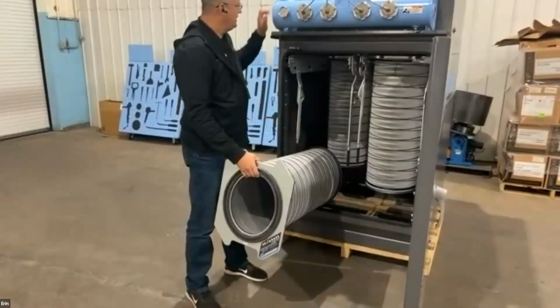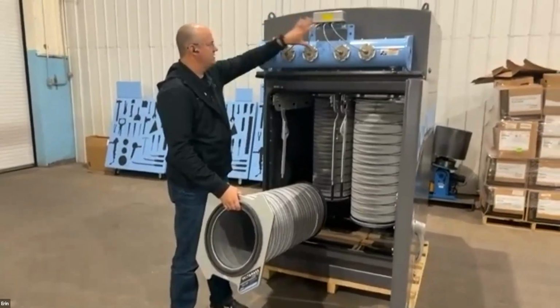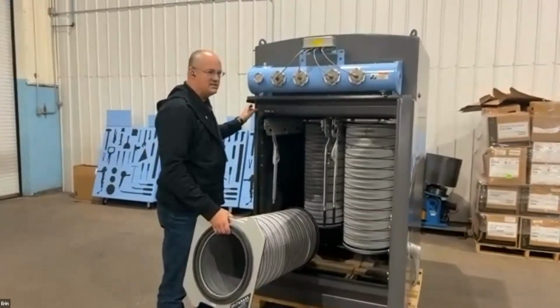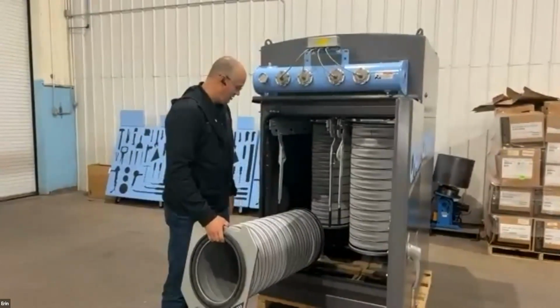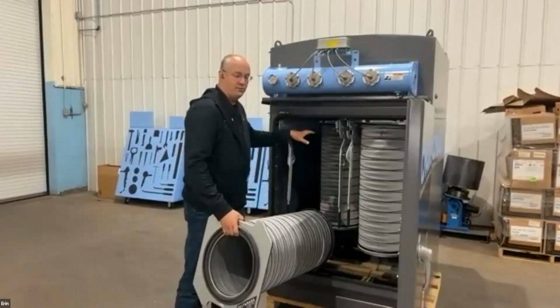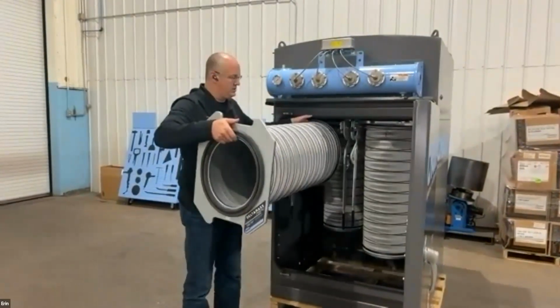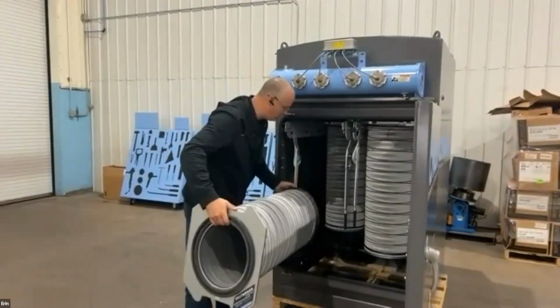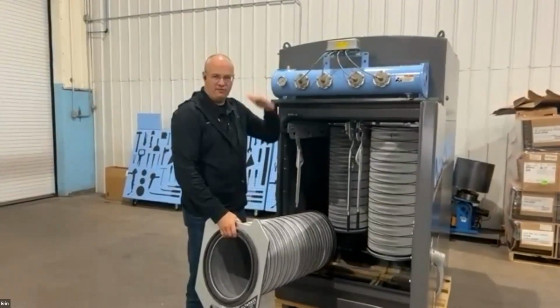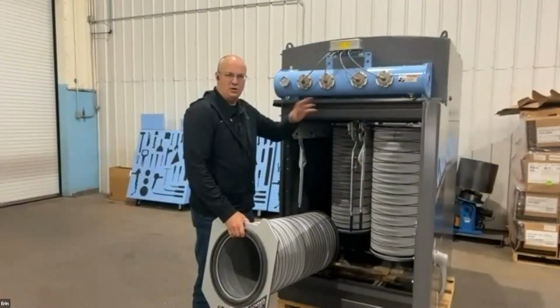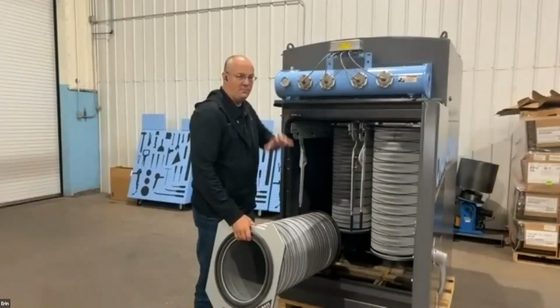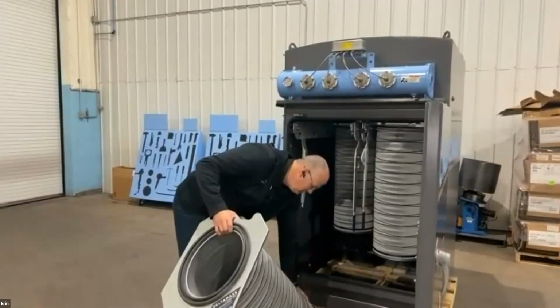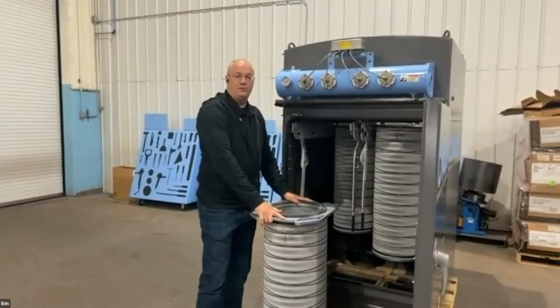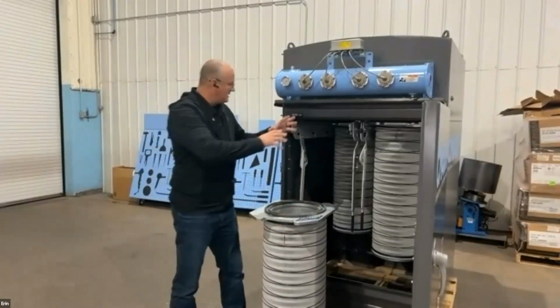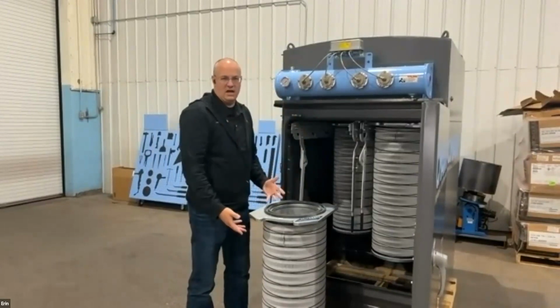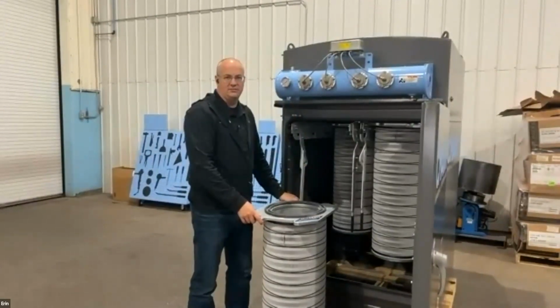So when those clean with the compressed air, there's compressed air that runs to this. When the collector senses that the filters are dirty enough through the pressure change, it pulses clean air down onto the filters. Now, in a horizontal style collector, it typically starts with the top one, and then it'll pulse down to the next one and pulse down to the next one. So you have a kind of cascading effect with the cleaning, almost like a slinky going down the stairs. The dust falls on top of the next filter. When you deal with a vertical style filter, one of the things you're going to see is that as it cleans, all of the dust just goes straight down into the hopper. So that's a little bit of an advantage of this style of collector.